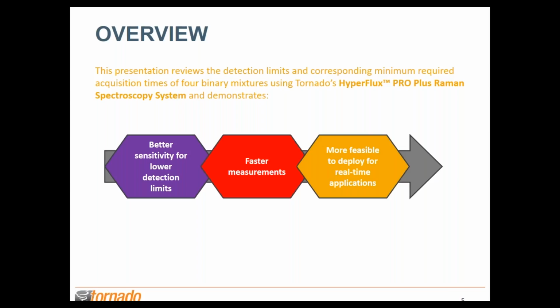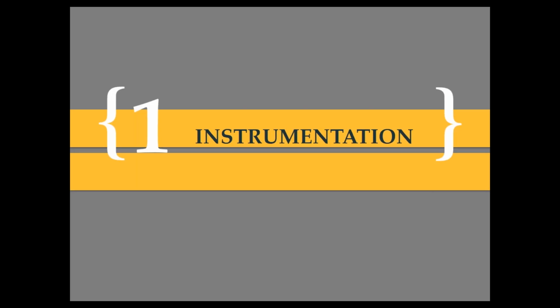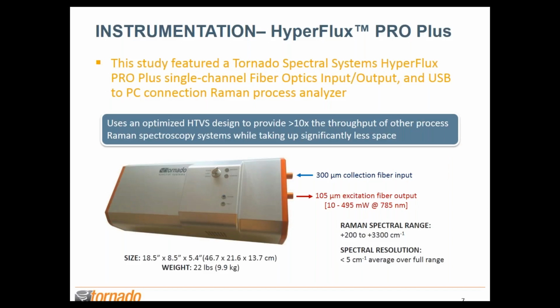First, I'll start with an overview of the instrumentation used for the study, the core of which is the spectrometer. This study featured Tornado's HyperFlux Pro Plus single-channel fiber optic process Raman analyzer that employs a USB to PC connection. The Pro Plus uses an optimized HTVS design that provides equal to or greater than 10 times the optical throughput in comparison to other process Raman systems, while doing so at a significantly smaller footprint, the actual size of the spectrometer.